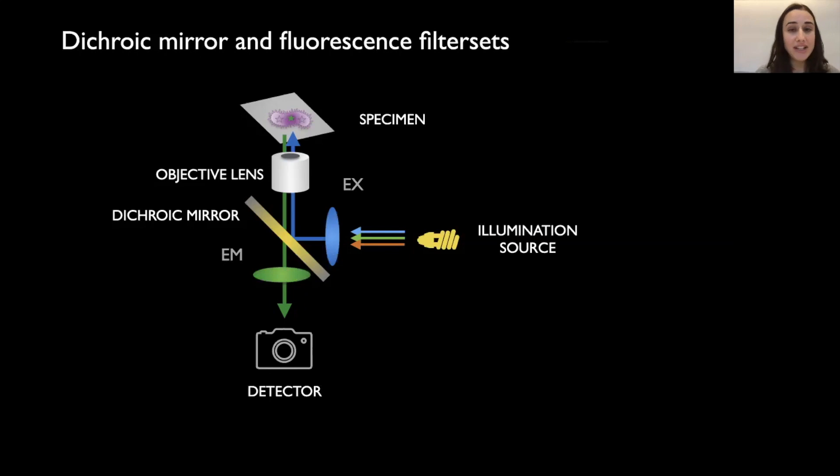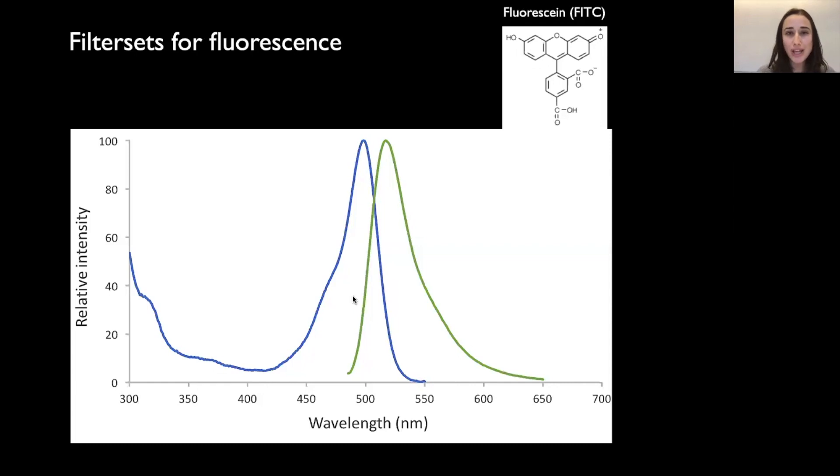But also in combination, the dichroic mirror is used in combination with the filter sets. So with the excitation filter and the emission filter, which will sit in the two optical paths. And the excitation filter will select just the wavelengths of the light used to excite our probe and the emission filter the same to select just the fluorescence. So how does this look like if we combine all together our fluorescence spectra from the dye? For example, here is still the FITC with filter sets and dichroic.